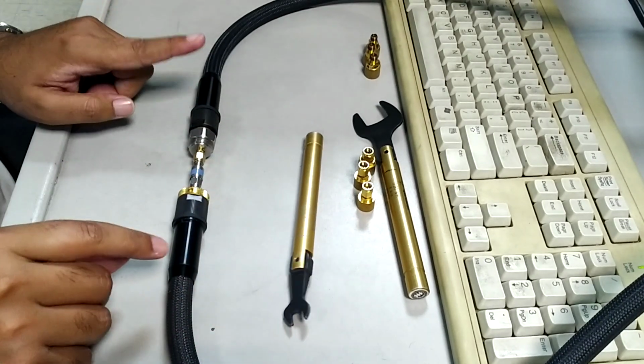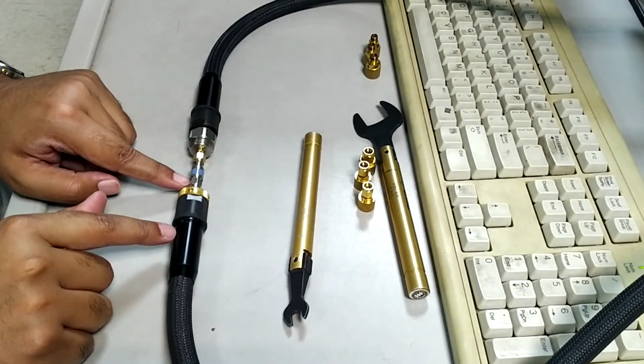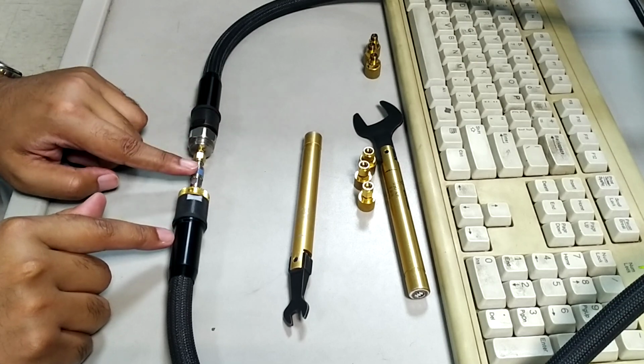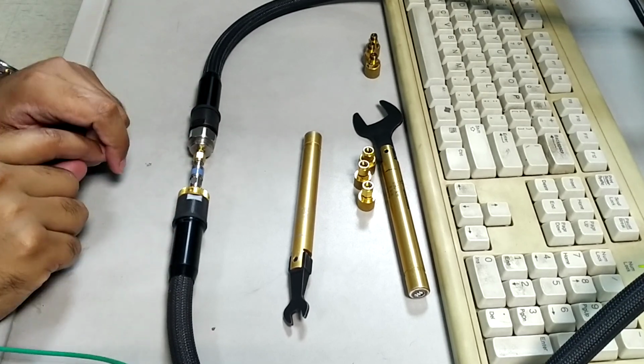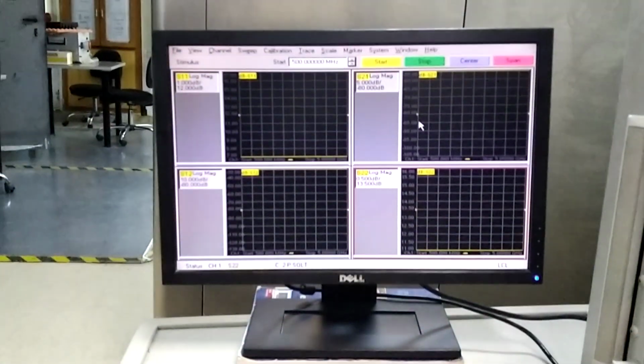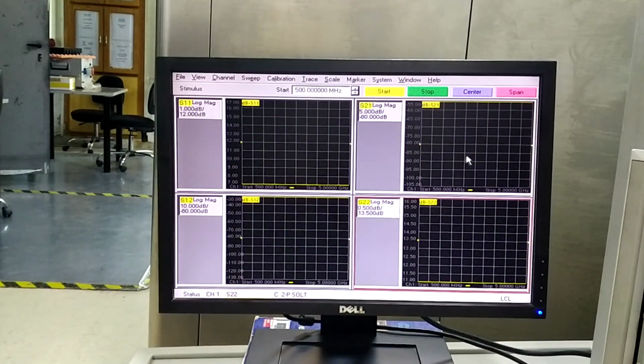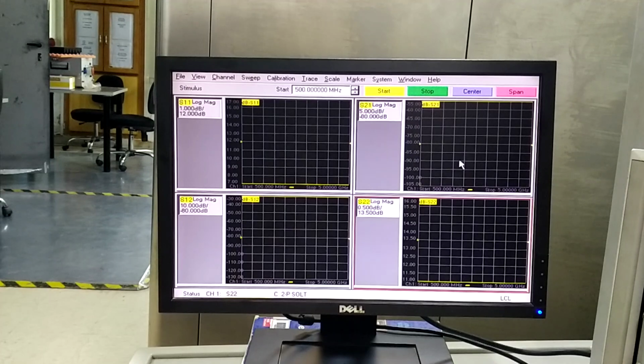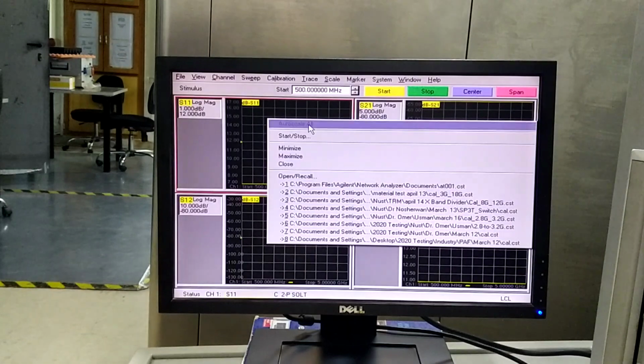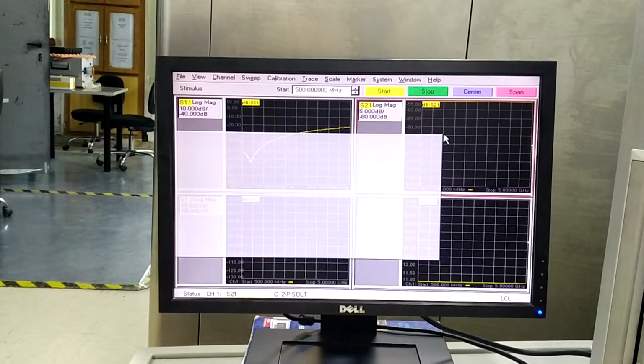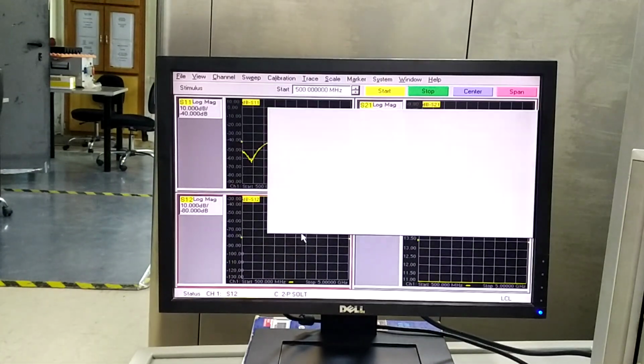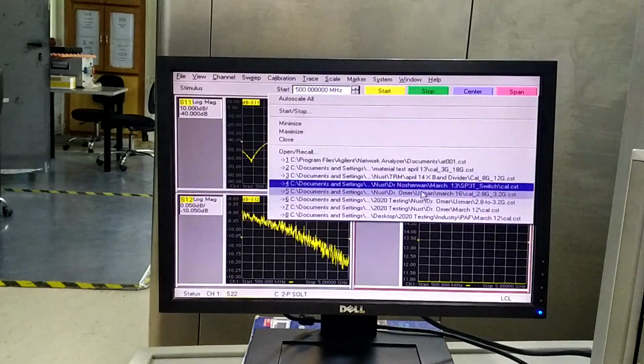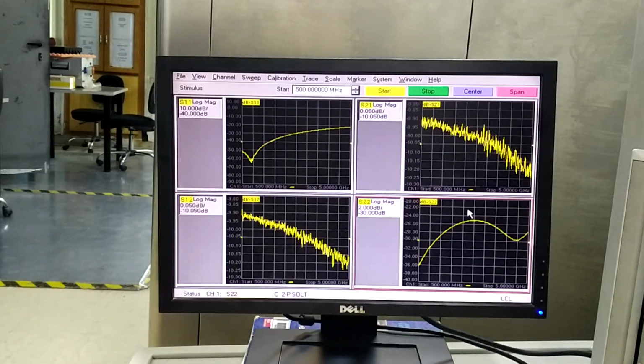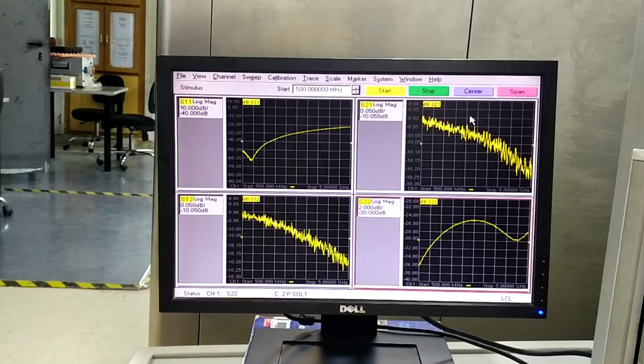So here you can see this is port number 1, this is port number 2, and the verification standard, which in our case is an attenuation standard, is connected. Now let's see the measurements of this attenuation standard. There's nothing displayed on the screen, which doesn't mean that the trace is not varying. It is varying, but the problem is that this trace is not auto scaled. So I just auto scale this one, this one, this one, and auto scale all. Here you can see all 4 parameters of the attenuator.